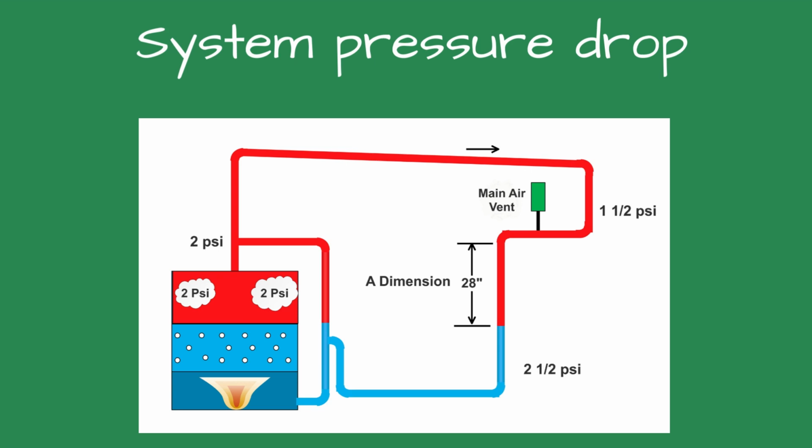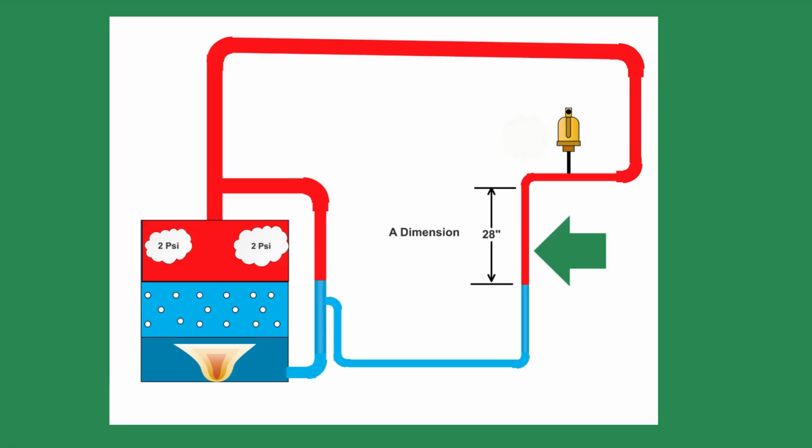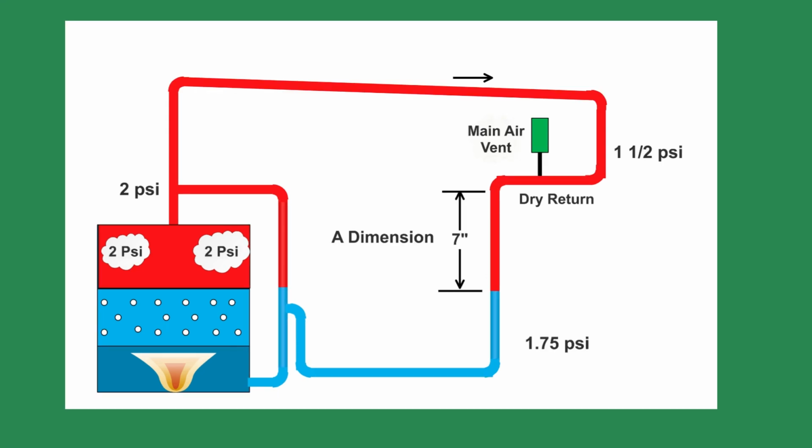In my commercial world, I could use a mechanical pump to push the water into the boiler. But the gravity return systems didn't have a pump. How did they get the condensate at 1.5 pounds into the boiler? The gravity return system uses a vertical pipe at the end of the steam run. The other end of the pipe is in the wet return. As the water begins to stack in the vertical pipe, the weight of the water starts to increase.